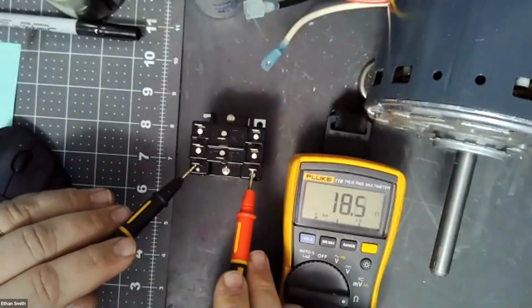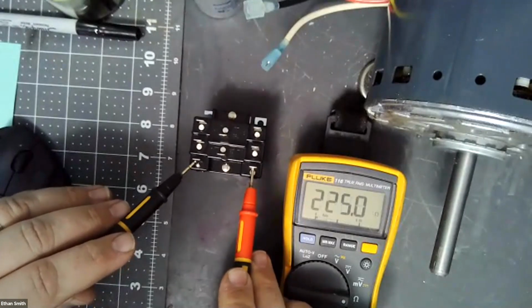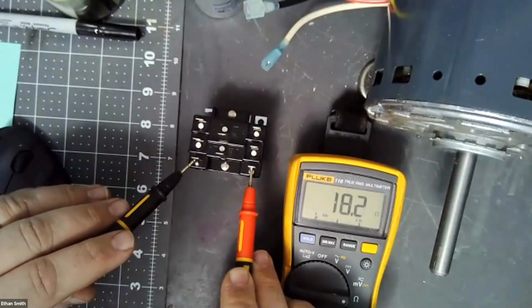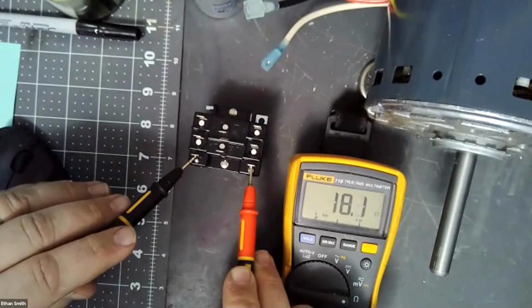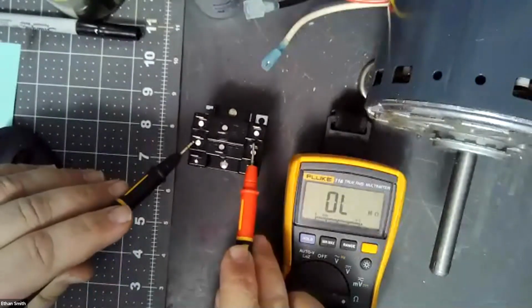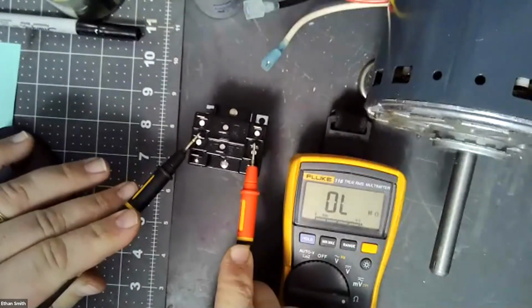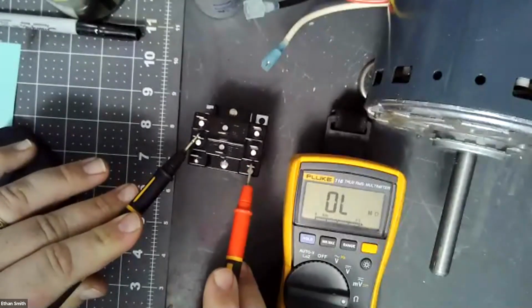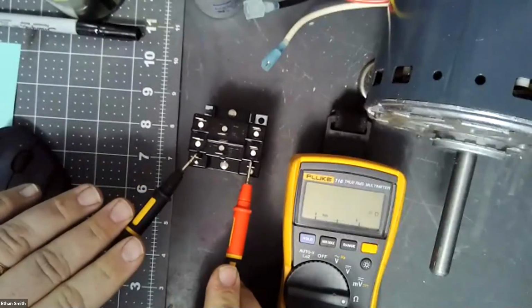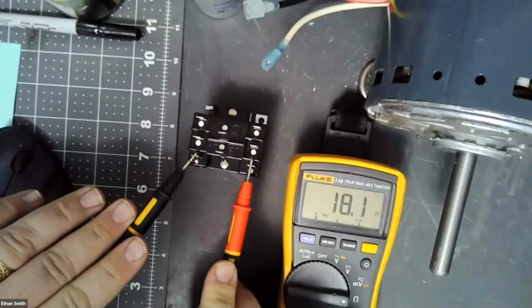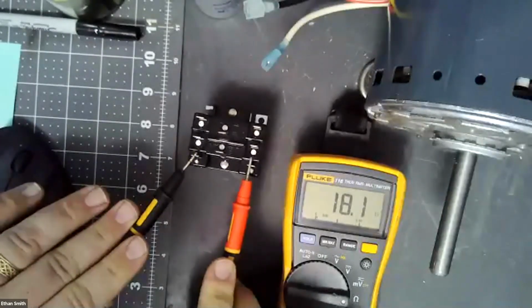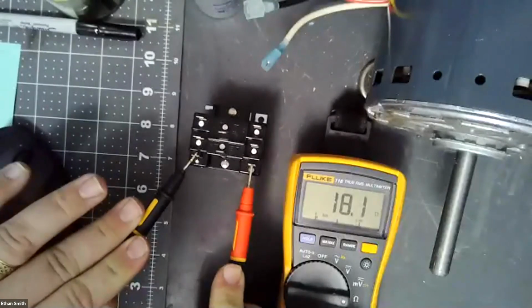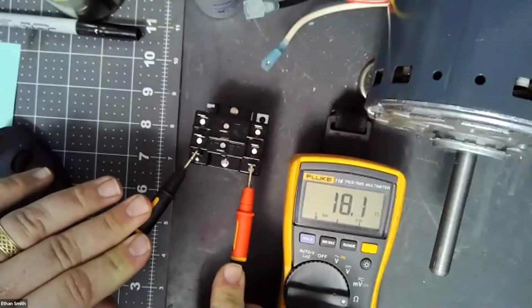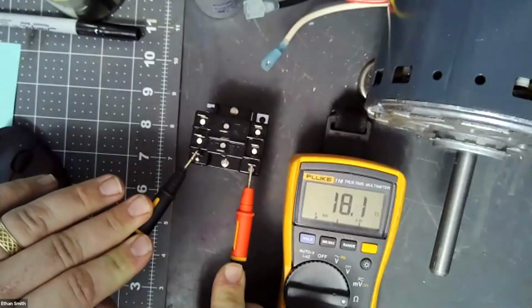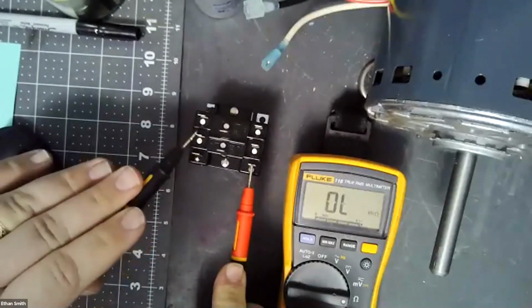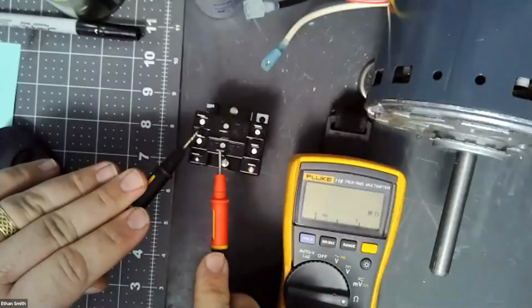So if we put our meter leads on this thing, we'll notice we have 18 ohms of resistance through it. Now, if we were to come up to this coil and it gave us an OL, we would know that that coil is broken somewhere, because we should have an electrical path through a coil of wire. Okay. So we don't know if this 18 ohms is correct or not, but we do know that it does have a coil there.